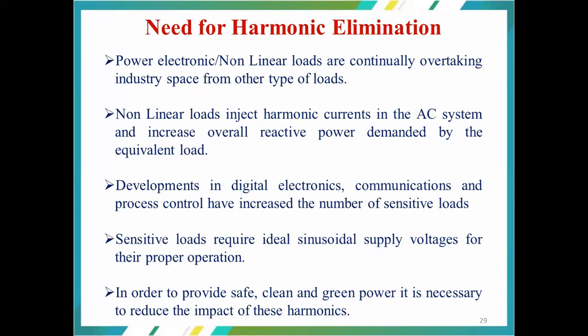And these nonlinear loads inject harmonic currents into the AC system and increase the overall reactive power demand by the equivalent load. Developments in digital electronics, communications, and process control have increased the number of sensitive loads. Sensitive loads require ideal sinusoidal supply voltages for proper operation, because any distortion in the voltage waveform or current waveform will predominantly affect their operation. So in order to provide safe, clean, and green power, it is necessary to reduce the impact of these harmonics. That means we improve the efficiency by reducing the effects of harmonics, reactive power, and the associated ill effects of these harmonic components.